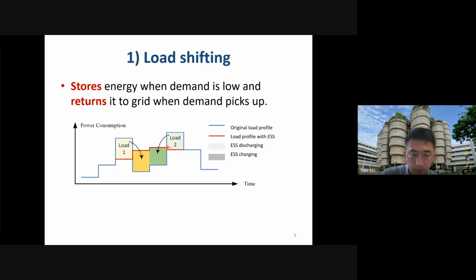For the second peak period we do the same: during this period we charge our battery, and after that, during the peak period, we discharge our battery. So the net total power demand becomes much smoother, and importantly, the net power consumption of the whole system becomes lower. By doing this, power utility companies do not need to expand their power infrastructure to satisfy such peak load - they only need to satisfy this red peak net demand. So they can save significantly on total investment cost.